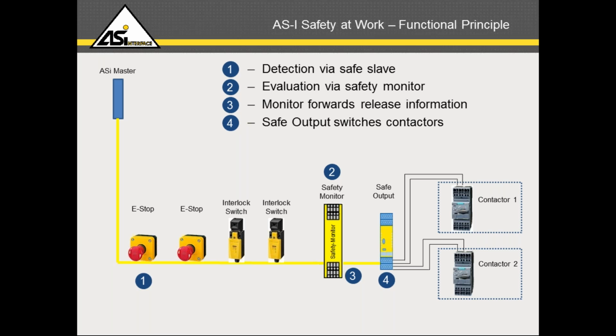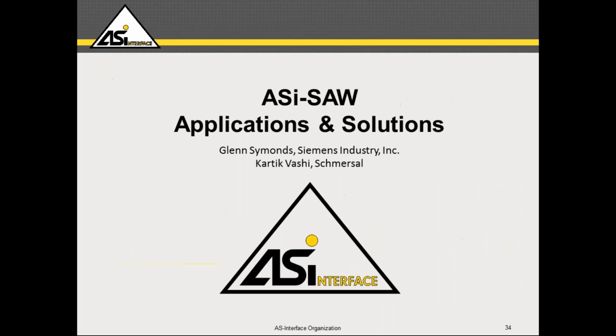So again, key is that the transmitted 32-bit code sequence must match what's in the safety monitor, otherwise the safety monitor prompts a shutdown or it reacts in the way that you've programmed it. So if there's any fault in a device, or an activation of a device, or loss of communication with the device, the safety monitor is going to prompt that safe shutdown.